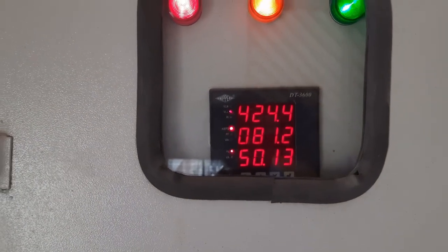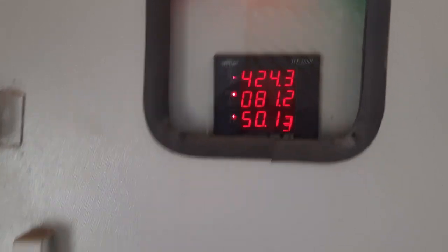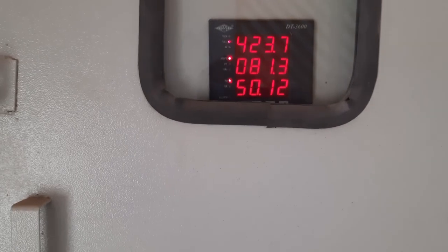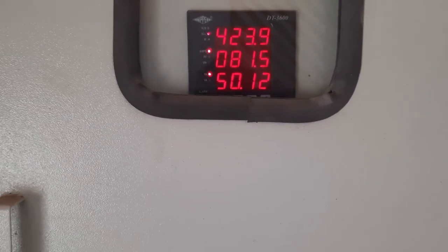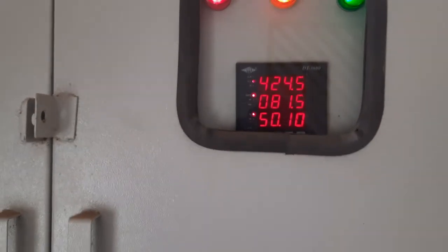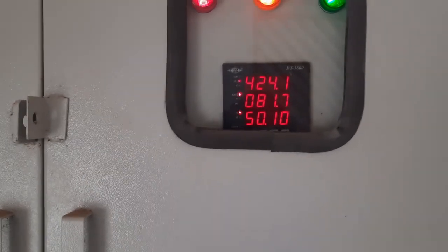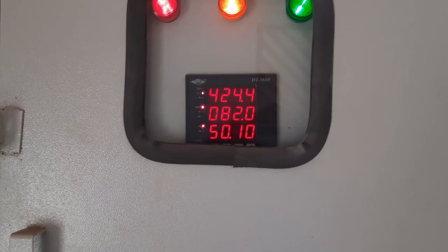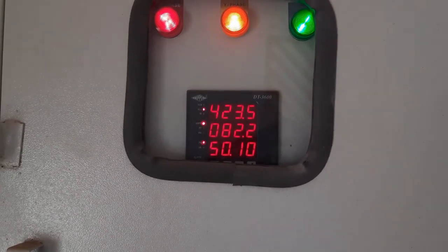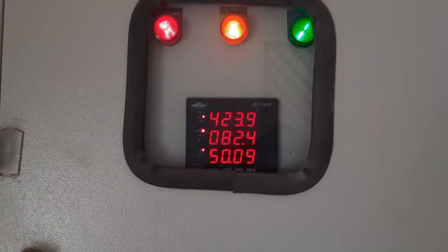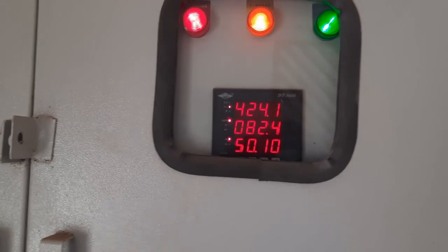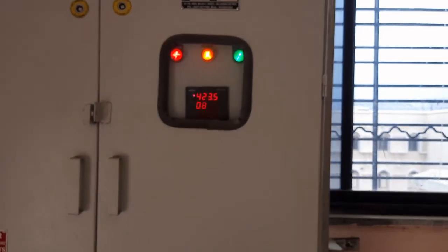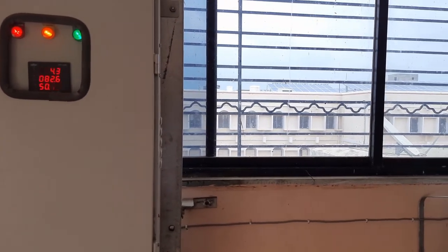All three inverter outputs are connected to the ACDB, where the ACDB gives some readings: 424 volt, delivering 81 ampere, and the frequency is 50.12 hertz. The current delivered by the three inverters depends upon the radiation. As soon as the radiation goes to a lower value, the output of the generator also decreases, but it gives better efficiency when the temperature is low and radiation is good, that is in the winter season. This is the overview, and this is the entire visit of the 295 kilowatt solar plant in the college building.